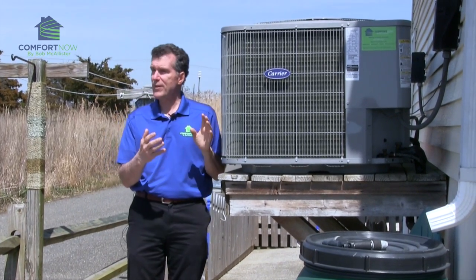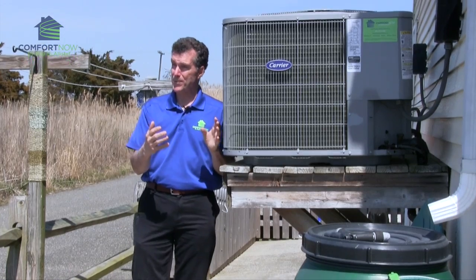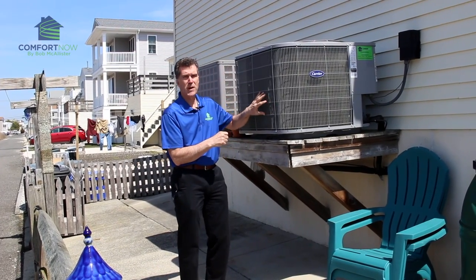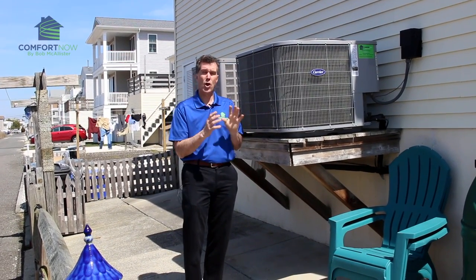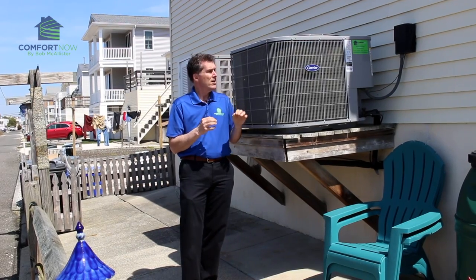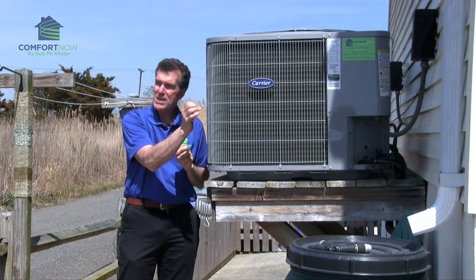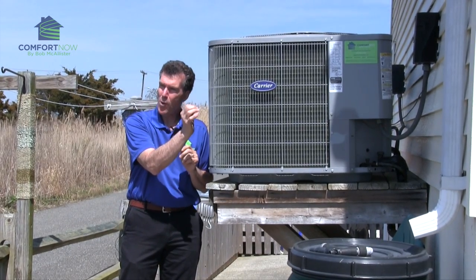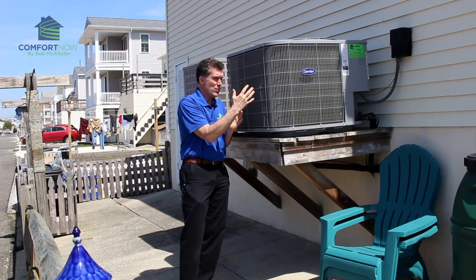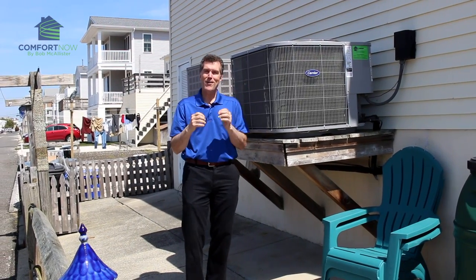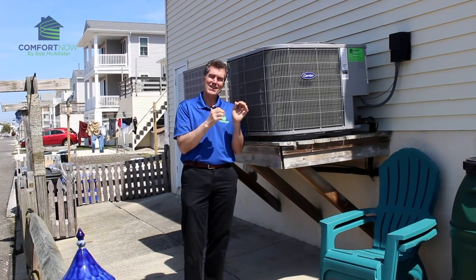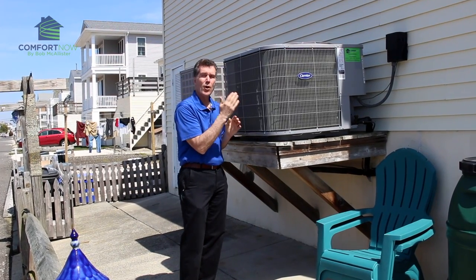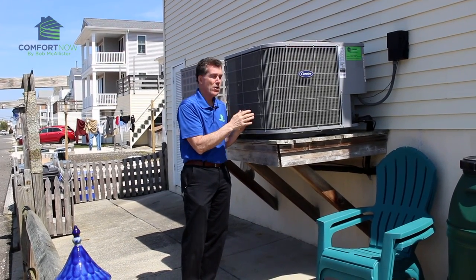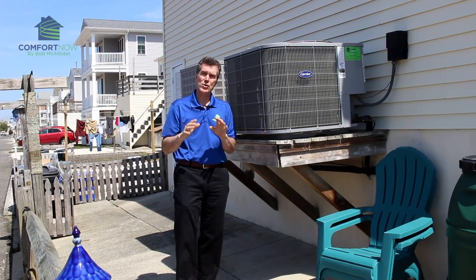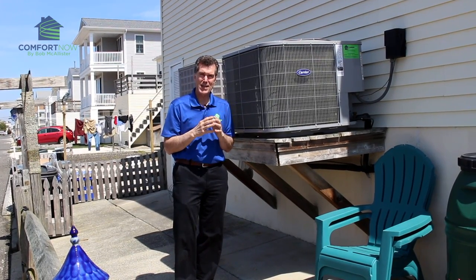This unit is specifically designed for the shore environment. It has a couple of key features. First, it has a special coating on the coil that lasts much longer in a salt atmosphere. Second, the coils are spaced just a little further apart. We still get the same heat transfer, but since salt air carries micro particles and sand, the extra spacing helps that material pass through and keeps the airflow going, which makes the unit run better, cost less to operate, and keep its capacity.